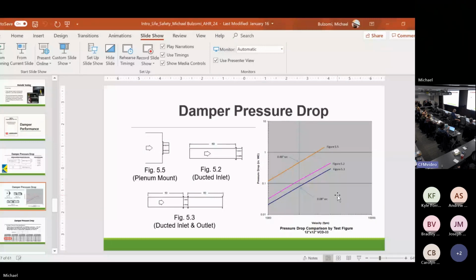It's not a rated size. They're only looking at the AMCA sizes. Nobody cares about the pressure drop of that damper. We all care about that. This is something that we're going to be working through AMCA, doing a little more exposure to the design world, and exposing the true pressure drop of the damper. So I just wanted to get you thinking about that.